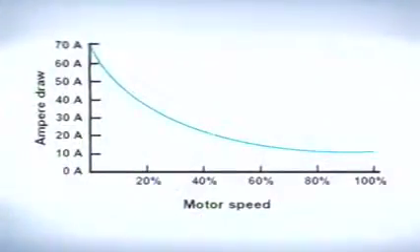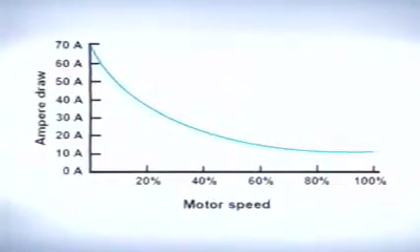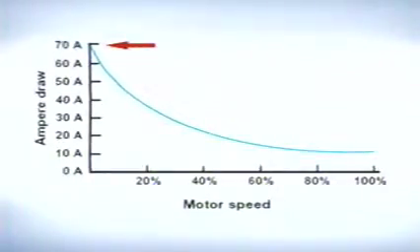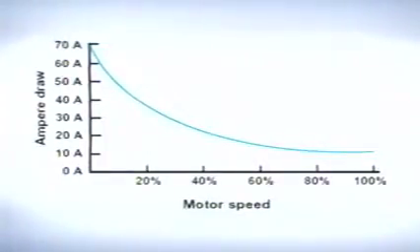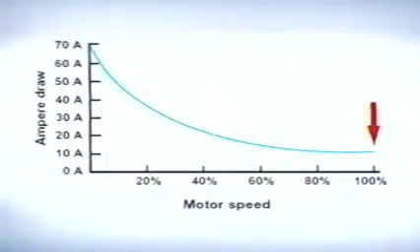When a motor is initially energized, it draws substantially more current than when the motor is running up to speed. For example, this motor draws close to 70 amperes when it's first energized — this is the motor's locked rotor amperage. As the motor reaches its design speed, the current draw drops down to its full load amperage.